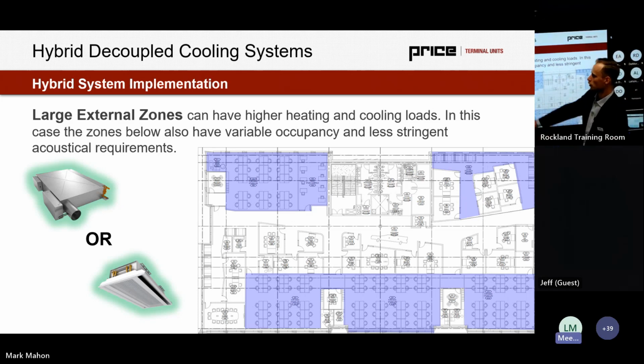Yeah, so the fan-powered box, and there's good rationale for that. So the fan-powered box in particular is really great for the variable load nature of this zone. I think that's a big benefit. The turn down of a fan-powered box is a little bit larger than the turn down of a chilled beam, whereas a chilled beam is much quieter. I think that's often a trade-off. So that could be an approach, and that was actually what I recommended in this case as well.